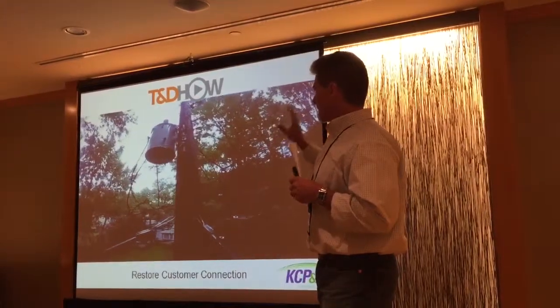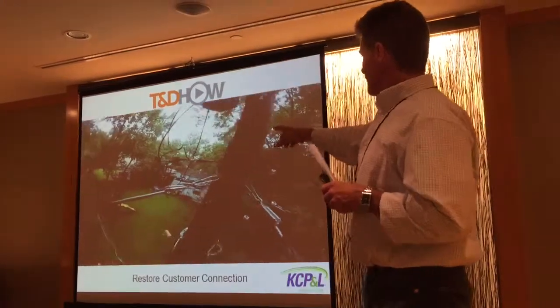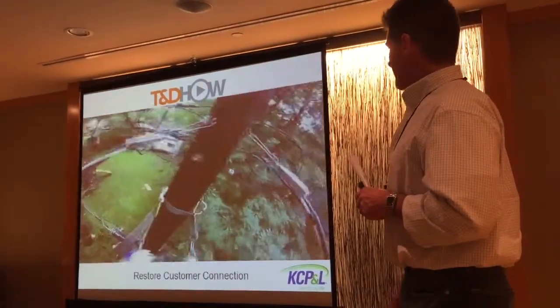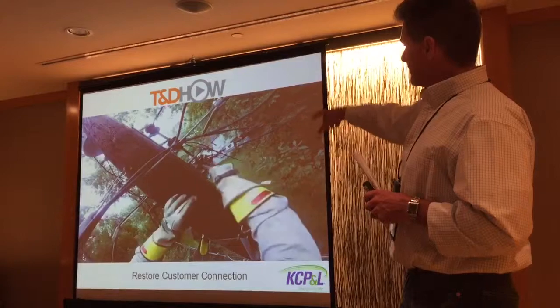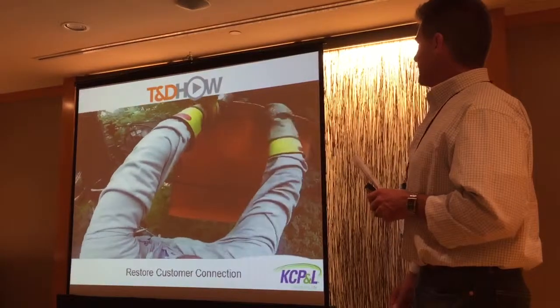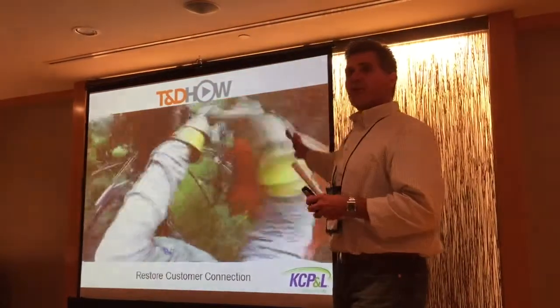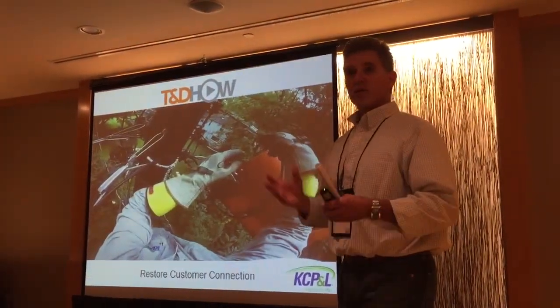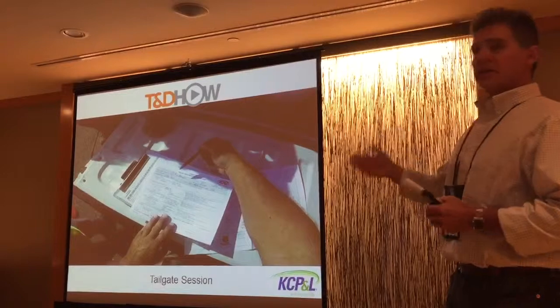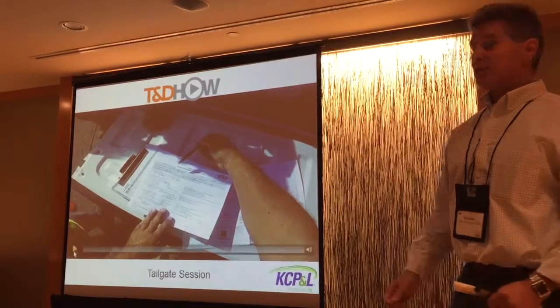This one here — the journeyman on the pole is actually going through his checks, looking at the fuse mounting, checking all the connections at the transformer. He'll sling underneath the service here on the right. He's looking at his ground connections now. You'll notice he'll point out the bottom coil to make sure it's not on the rack. Then he'll go ahead and cover up the open wire. This is perfect for a cold apprentice to see. Some of these things can be tailored to you — just put it on your guys wherever they're working, and you've got the video in the library.